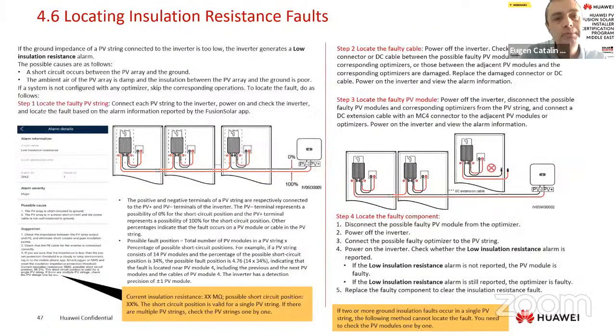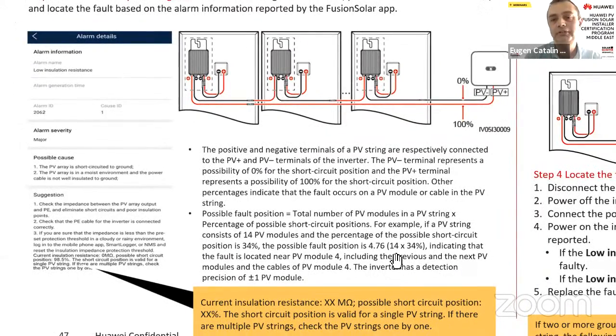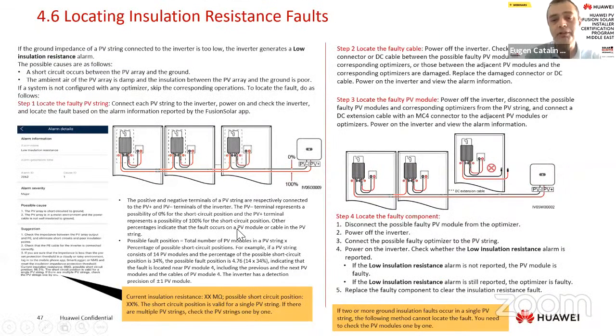With the new optimizer and new products, we now have locating of insulation resistance faults. If we have this kind of alarm, in the alarm suggestion here we have a percentage that we multiply with the number of PV panels, and we can see where the fault can be. For example, we have a case here, 14 PV panels, 34% multiplied gives around panel number 5. There I need to check the fault.